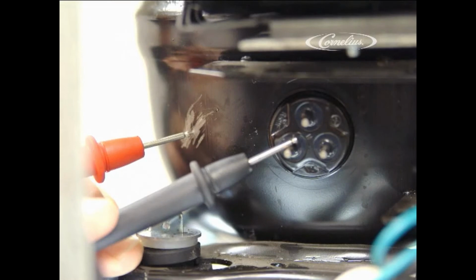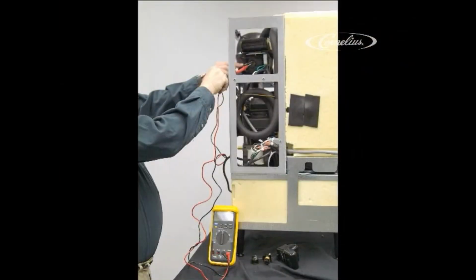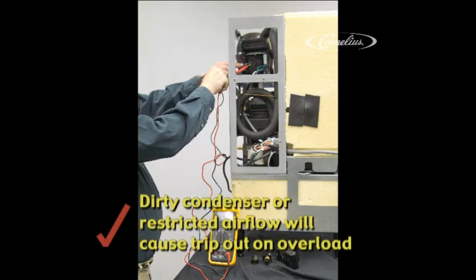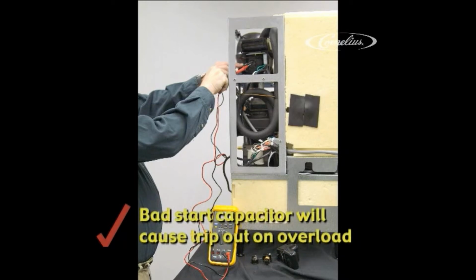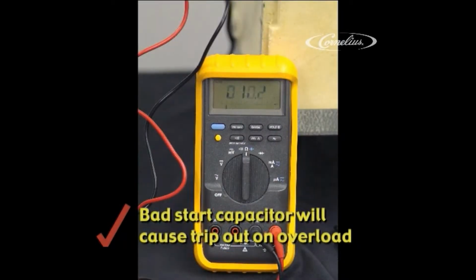Now we need to check each post to the compressor shell to be sure there is no grounding to the compressor shell itself. Scratch the paint off the compressor to be sure of a good contact and measure each post. They all should read infinity. If resistance reads 0, then there's a direct short and the compressor will need to be replaced. Check the overload for signs of overheating. A dirty condenser or restricted airflow to the unit will cause the system to trip out on the overload. Also, if the start capacitor is bad and not discharging, this could be another cause for the overload to trip the system as stated above.